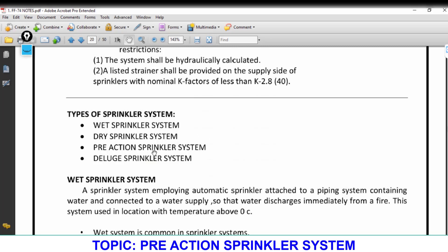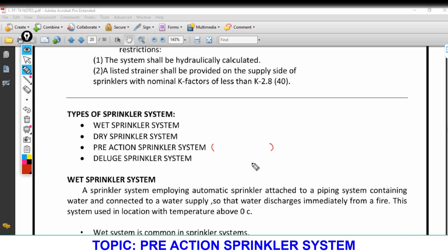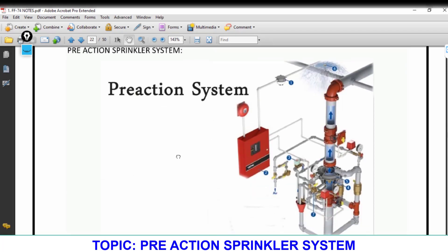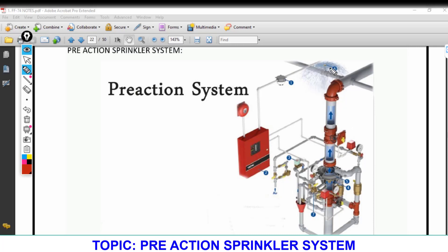In areas where accidental sprinkler damage is a risk, we use the pre-action system. Remember, pre-action is also a type of dry sprinkler system. In this system there are two circuits: Circuit 1 contains the sprinklers — upright or pendant type with a sprinkler bulb — and Circuit 2 contains heat detectors installed in parallel with the sprinklers.